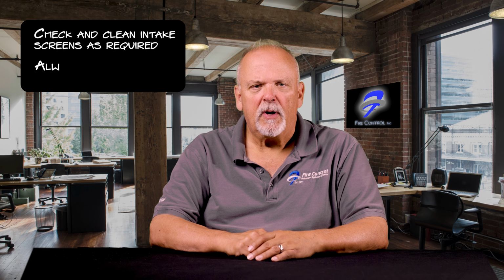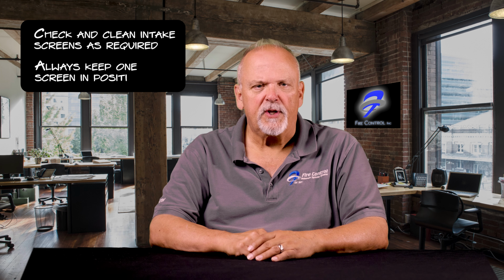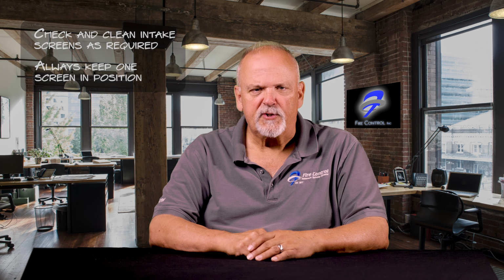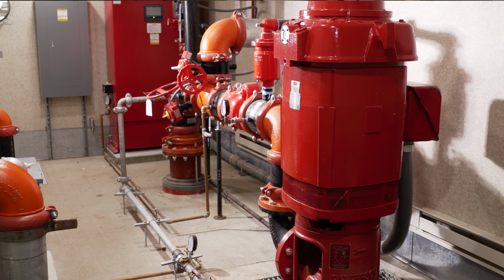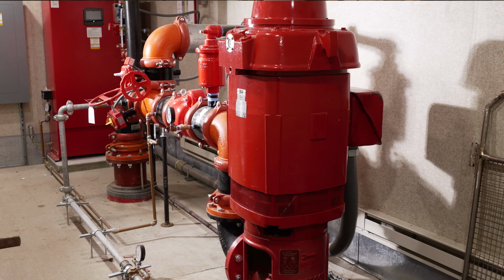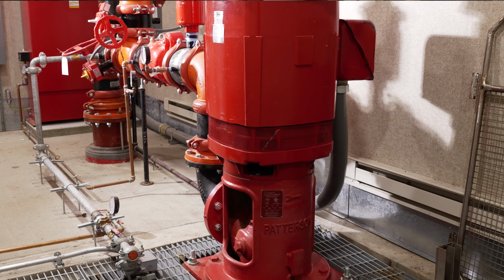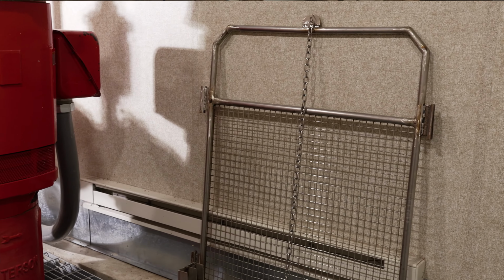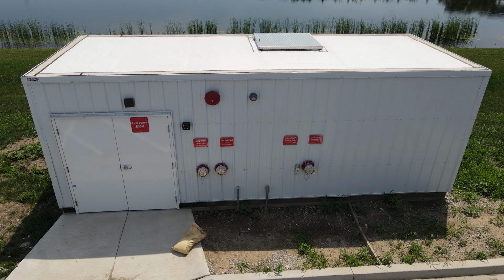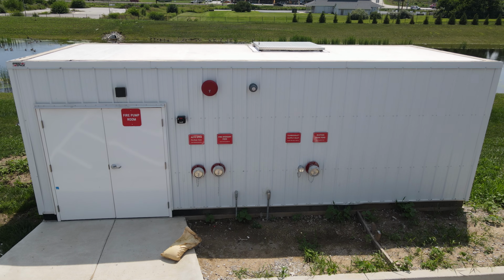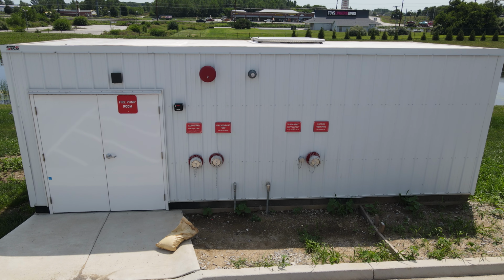At any point in time, one of the screens must be in the lowered position, with one screen in the sump. The other should be cleaned and kept ready for the next cycle, when the cleaned screen would be lowered first and the opposite screen then be extracted. The fire pump and jockey pump require weekly, monthly, quarterly, and annual checks, tests, and inspection. This is all set forth by NFPA 25 and will be part of regularly scheduled maintenance. On the outside of the pump building, there are several connections of different types. These are for testing and fire department use.